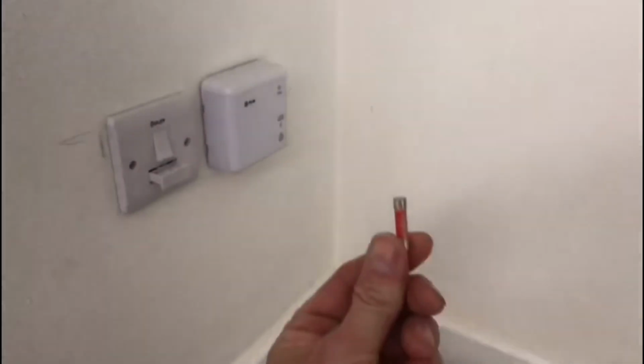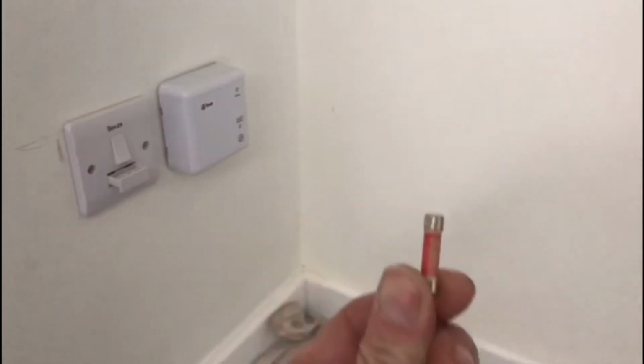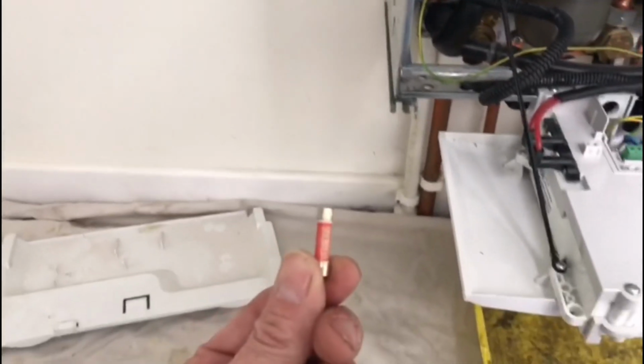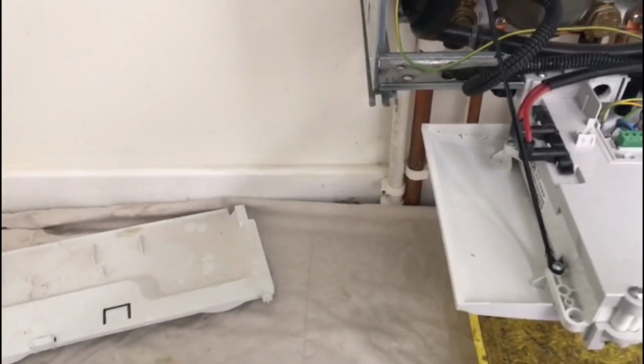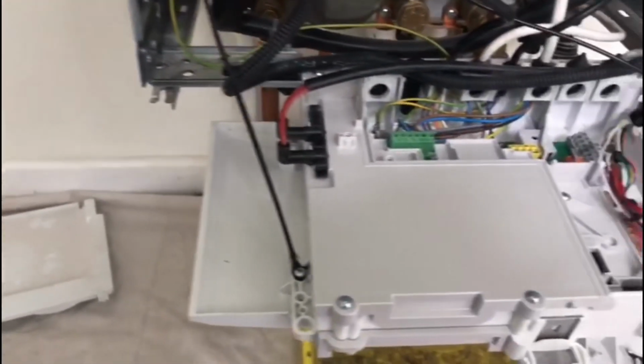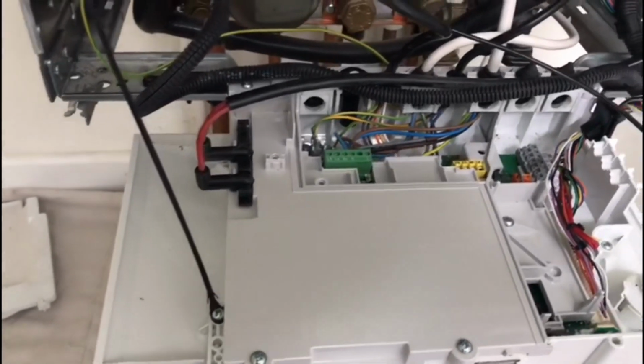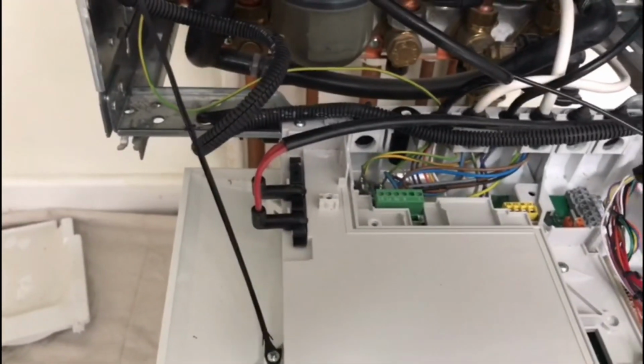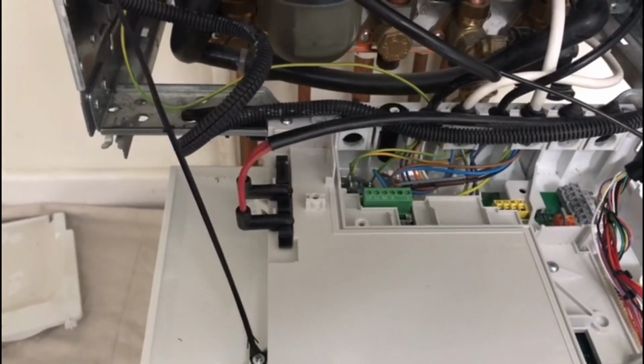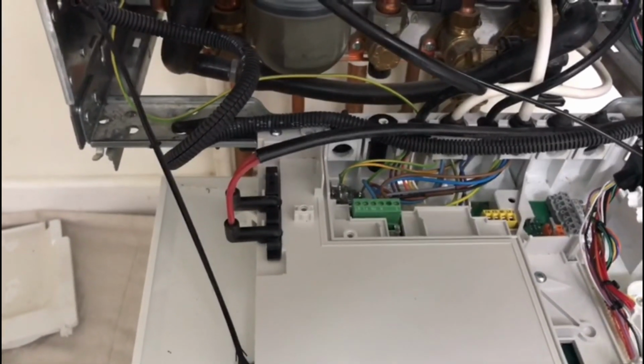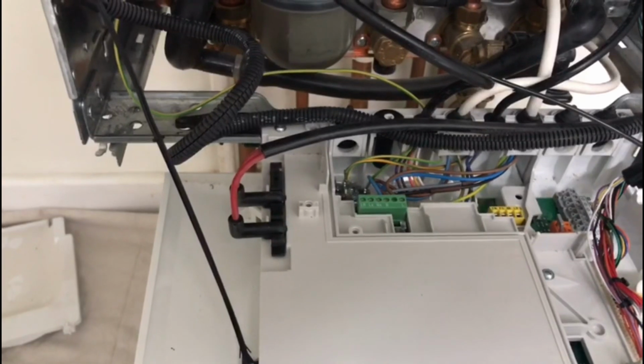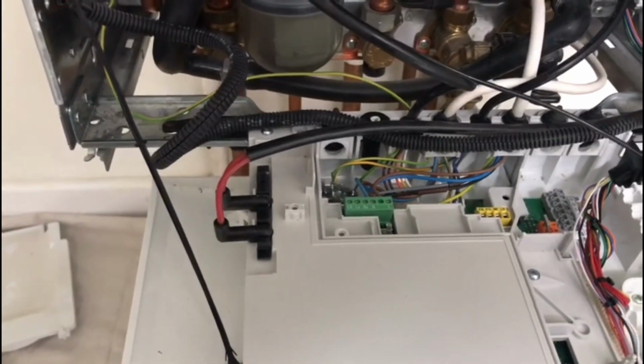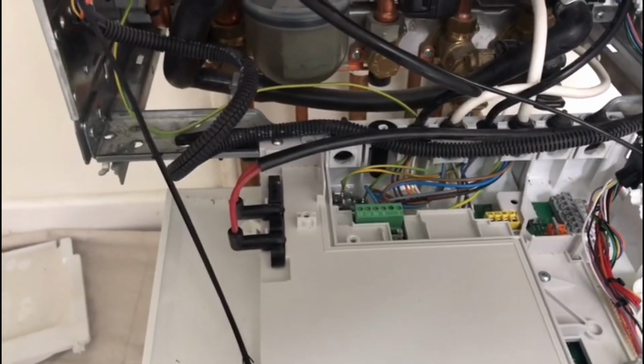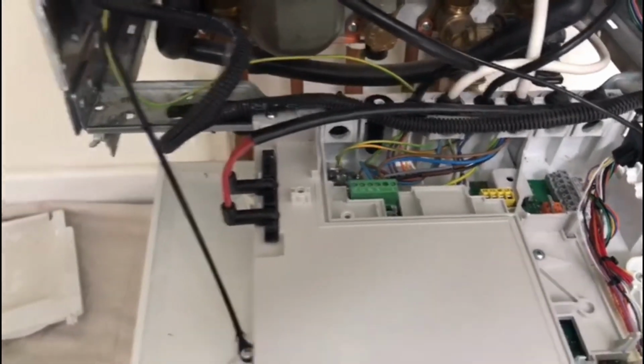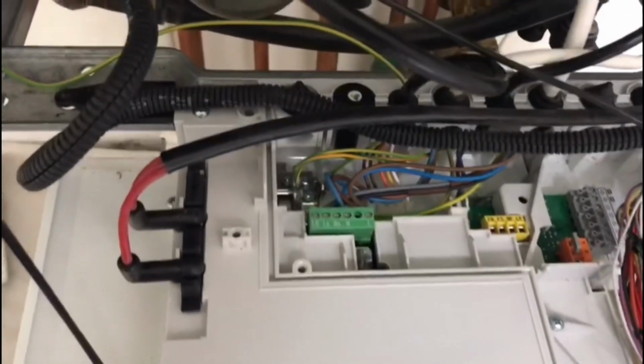Now I've removed the fuse from the boiler. Some people do it differently, but I always choose to put it in my pocket. So the 3 amp fuse is in my pocket. What that means is that I've got control. Unless somebody comes in, beats me up and puts me in a bad state and puts the fuse in without me knowing, then I know that the 3 amp fuse is in my pocket and that no one can turn the electrics onto the boiler. So basically it's a pretty straightforward one.